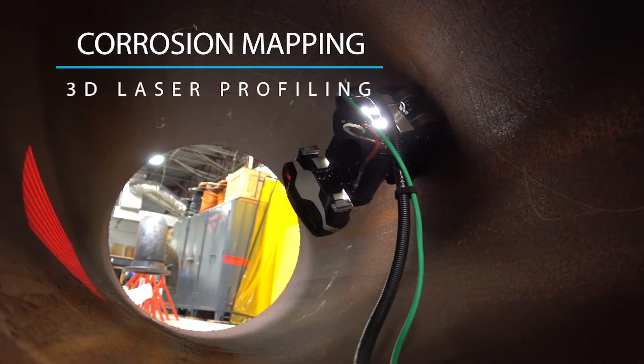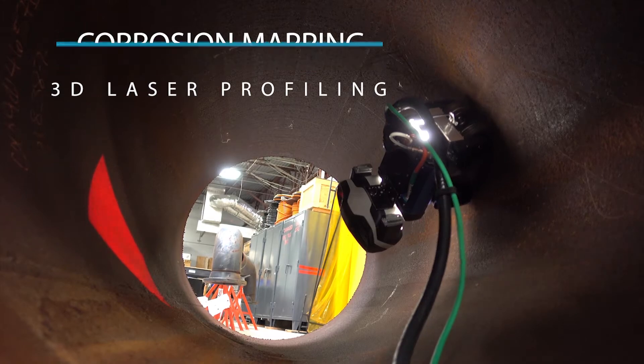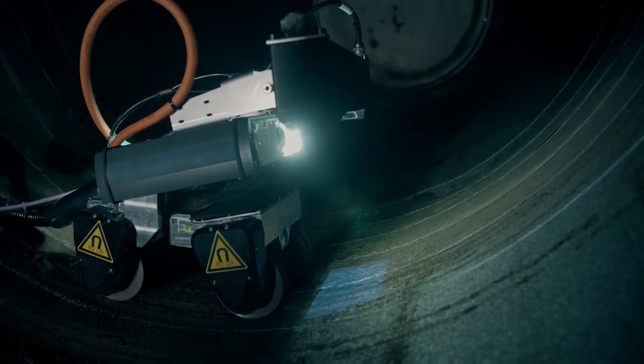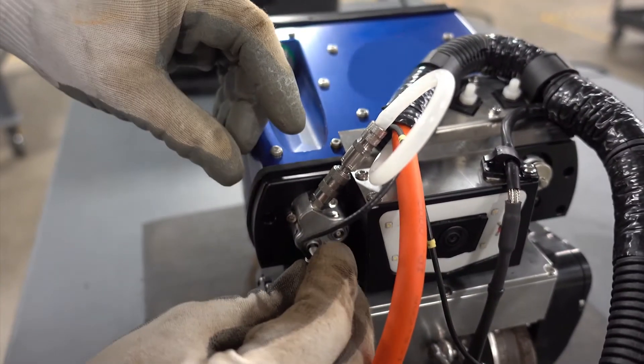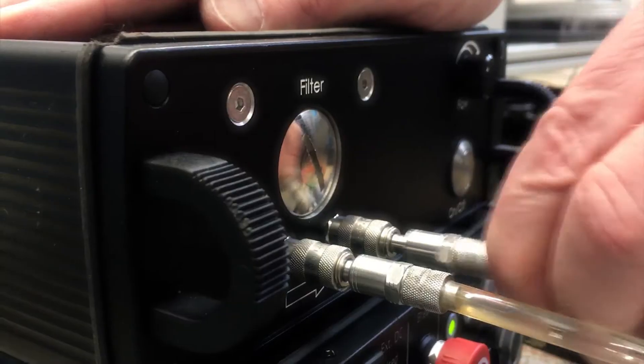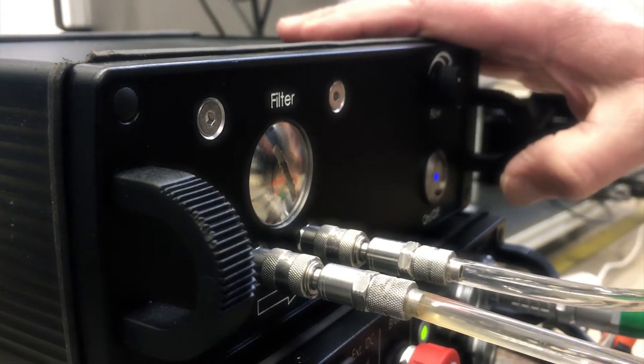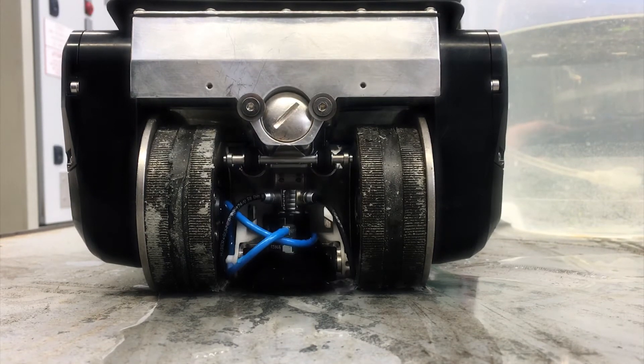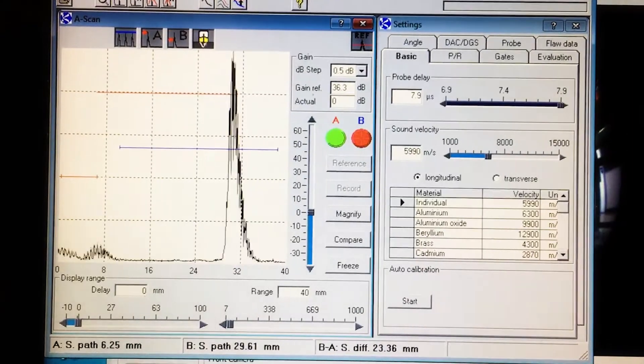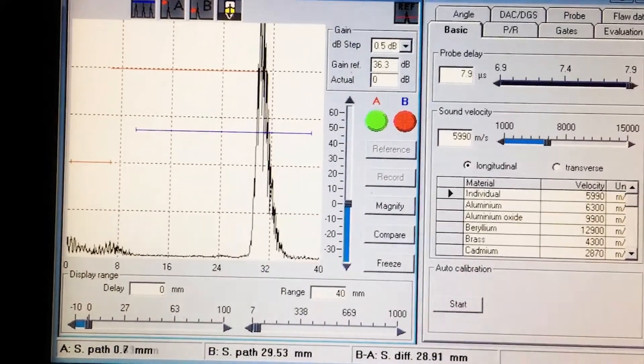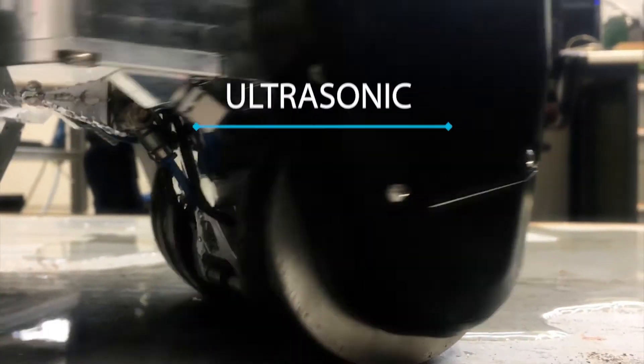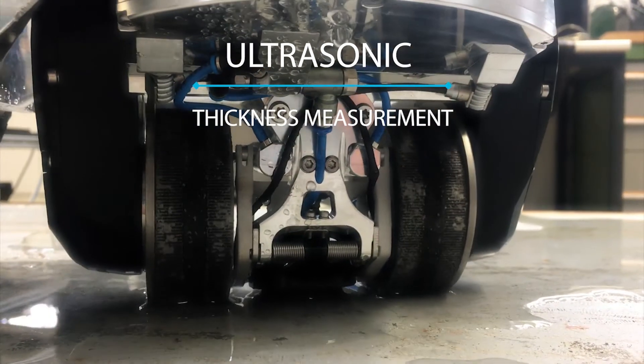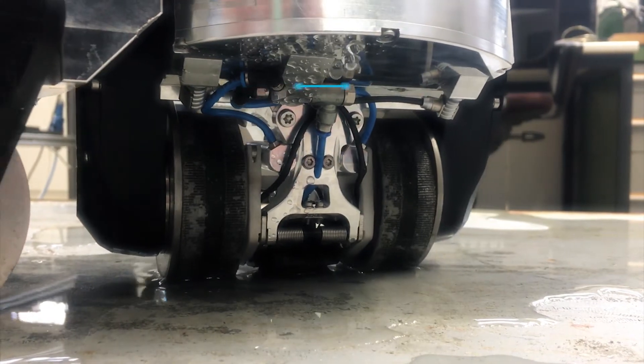Depending on the inspection tasks and environment, several modules are available. An ultrasonic probe holder module can be mounted in between the front wheels for accurate thickness measurement. The module is actuated remotely by a couplant pump that lowers the probe onto the surface. Additionally, water is routed to the probe head as excess couplant for the ultrasonic transmission.